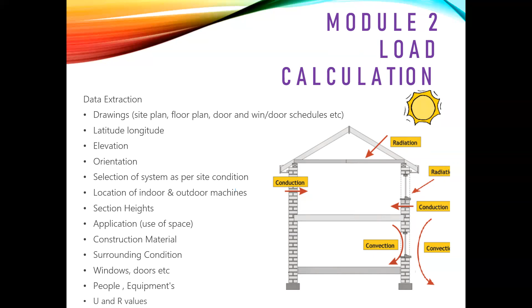So after collecting all this data, comes load calculation, which is also a very important topic. First, we will look at a simple project, and we will use manual equations to calculate the load of that area. And we will be using ASHRAE handbooks and climatic data software. As I told you earlier, we have different software for getting climatic data, psychrometric data, etc. We will use all that, and we will consider all these internal and external sources. Internal and external sources are nothing but sources which are producing heat. Okay, we have to consider that. And based on these equations, we will calculate the heat load. Infiltration and ventilation requirements are also there. Ventilation, as I told you, is air which we are bringing from outside, and infiltration is unwanted air coming inside the building through doors, cracks, etc.